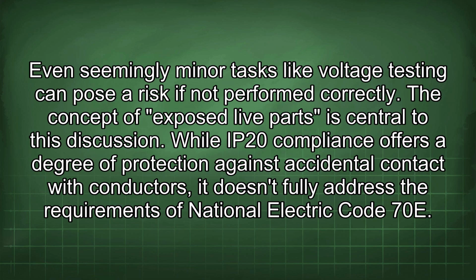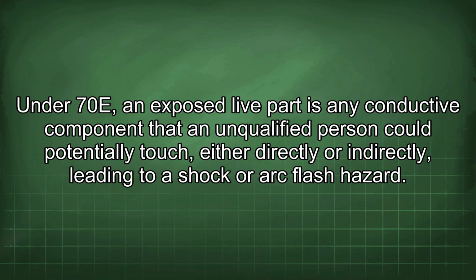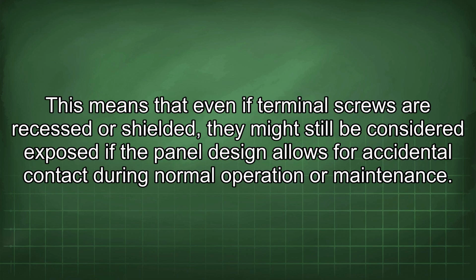While IP20 compliance offers a degree of protection against accidental contact with conductors, it doesn't fully address the requirements of National Electric Code 70E. Under 70E, an exposed live part is any conductive component that an unqualified person could potentially touch, either directly or indirectly, leading to a shock or arc flash hazard. This means that even if terminal screws are recessed or shielded, they might still be considered exposed if the panel design allows for accidental contact during normal operation or maintenance.